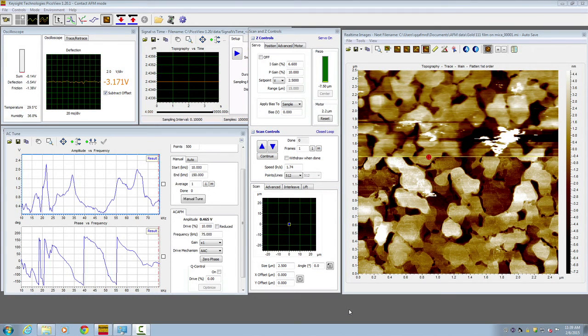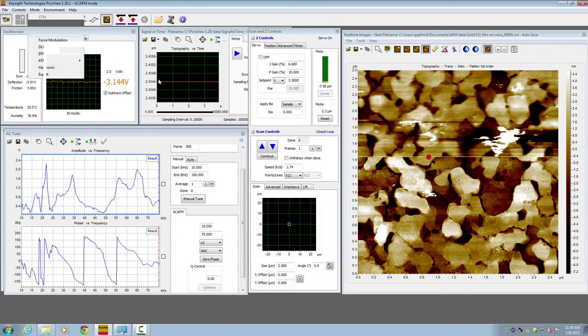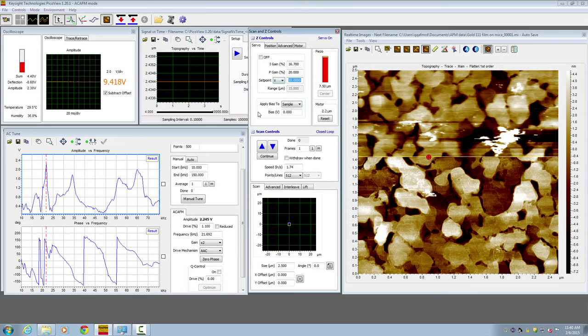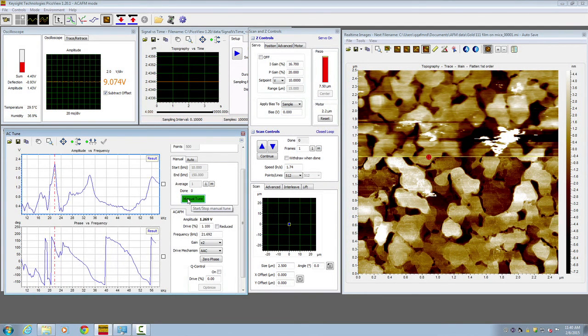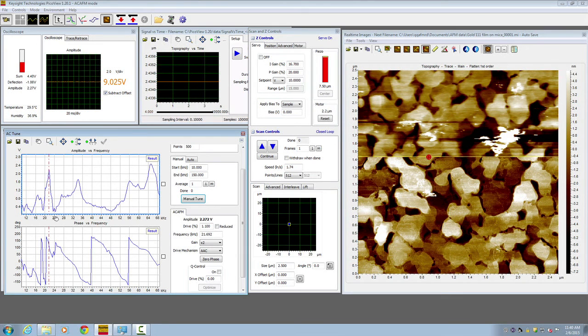Using the exact same contact mode cantilever, we could also perform AC mode in liquid. No cantilever changes needed. Here's how. On the software, switch to AC mode, put your set point at 10, so the tip will pull back, and then perform a manual tune. Here we find a very nice peak between 20 to 24 kilohertz, and we put on the peak, which is around 21 kilohertz.